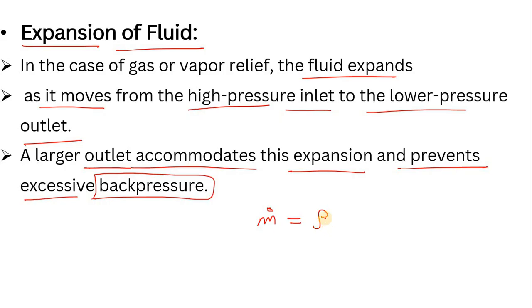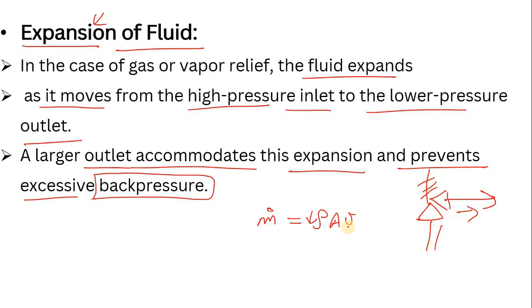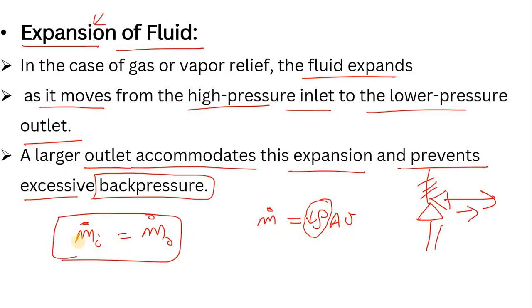Now, looking at the continuity equation: mass flow rate equals density times area times velocity. As I said, when the fluid expands, the density is reduced. If the system becomes over-pressurized, the fluid relieves from inlet to outlet. Mass is conserved — the mass flow rate at inlet equals the mass flow rate at outlet. As density decreases, velocity increases, so to accommodate this, the area must be increased.